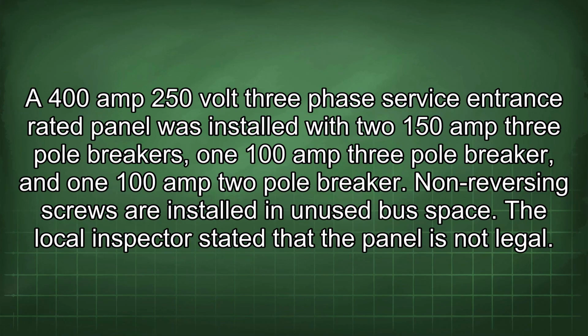A 400 amp 250 volt 3-phase service entrance rated panel was installed with two 150 amp 3-pole breakers, one 100 amp 3-pole breaker, and one 100 amp 2-pole breaker. Non-reversing screws are installed in unused bus space. The local inspector stated that the panel is not legal.